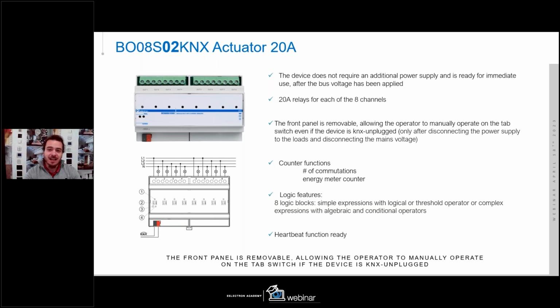So this is, let's say, a classic 20 amp relay, where we also have some counter functions, starting from the number of commutations, which means that we can count how many times the relay is opened and closed, or only opened or only closed. We can reset this value, which means that we can decide when we want to start counting how many times the light or the contact is closed or open. And we also have a calculated energy meter counter. I say calculated since there is no energy meter inside this device, but we have the opportunity to calculate, let's say, energy consumption. This is because we can say in the ETS parameters that the output will consume 100 watts, and in this way we can calculate how many kilowatt hours the output will consume.